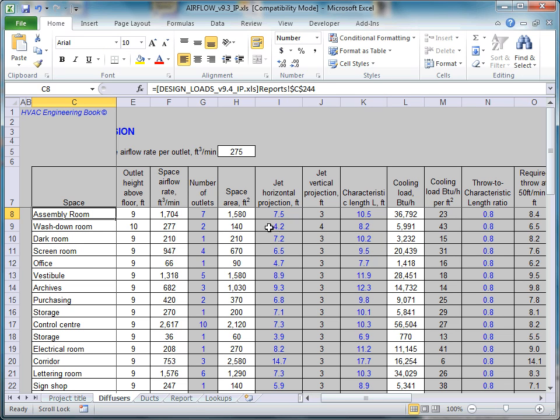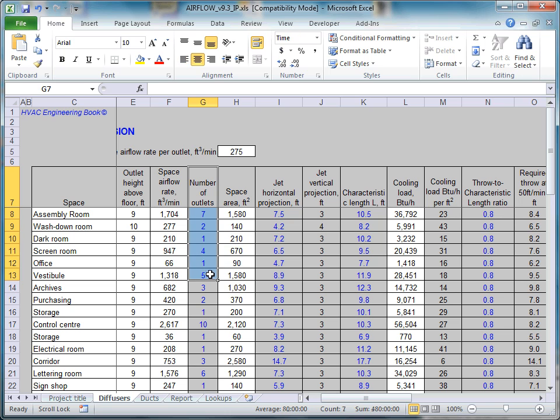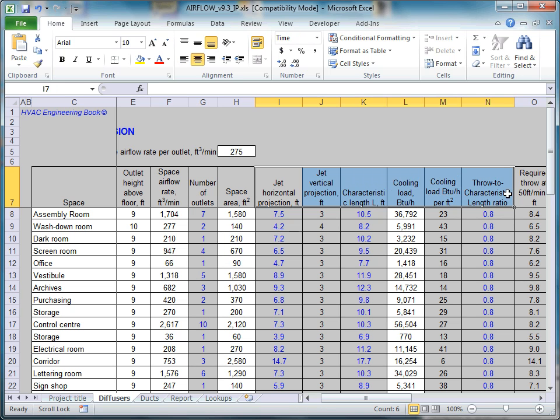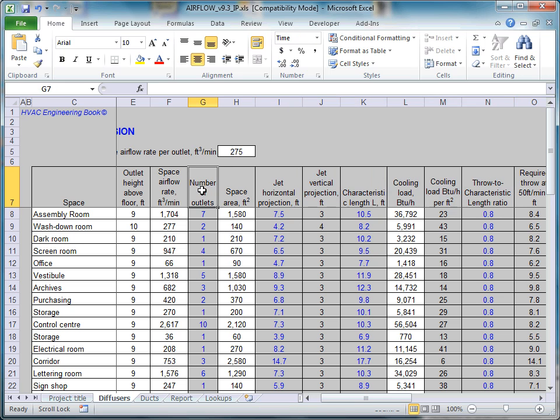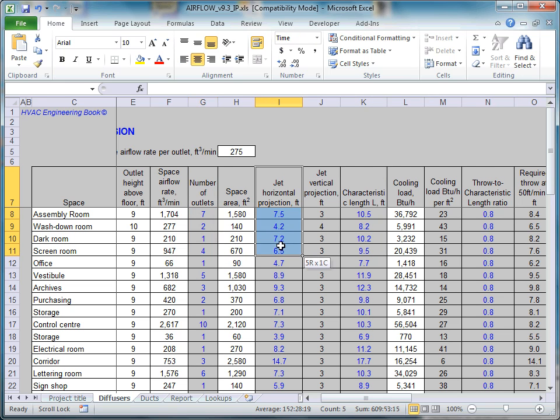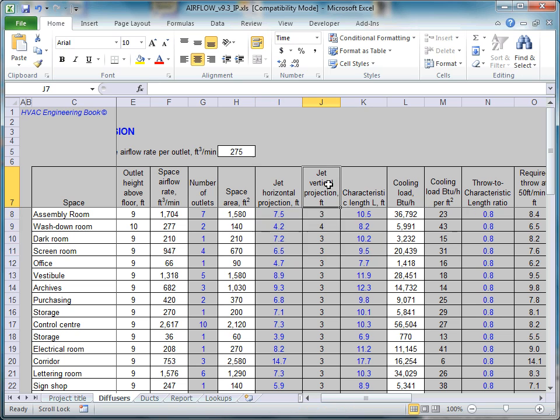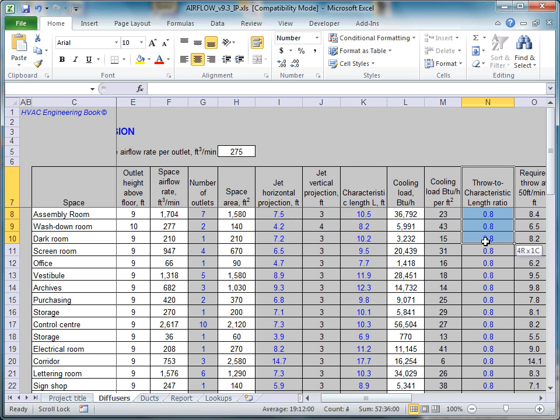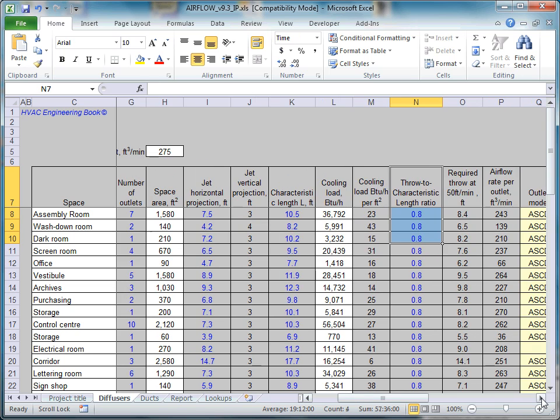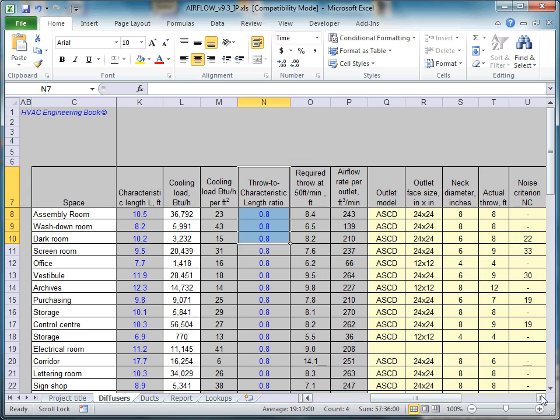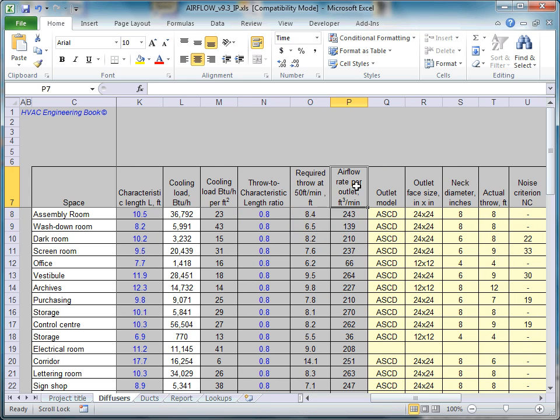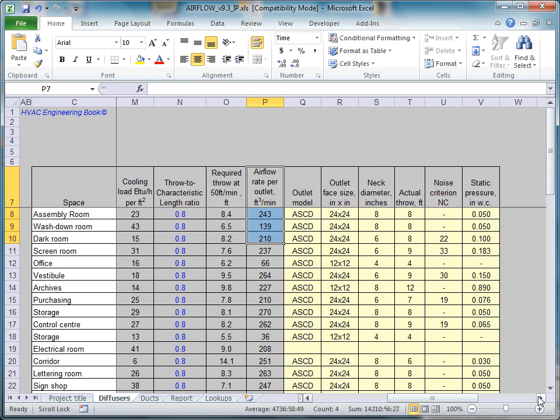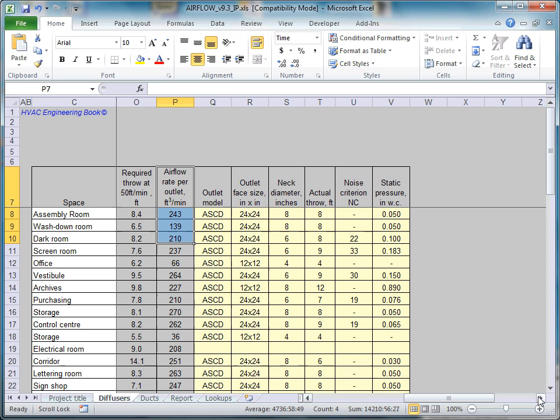We see that the software has calculated a suggestion for the optimal number of diffusers for each space and their recommended characteristics: Number of Outlets, Horizontal Jet Projection, Vertical Jet Projection, Characteristic Length, Throw to Characteristic Length Ratio, Throw at 50 FPM, and Airflow Rate Per Outlet.